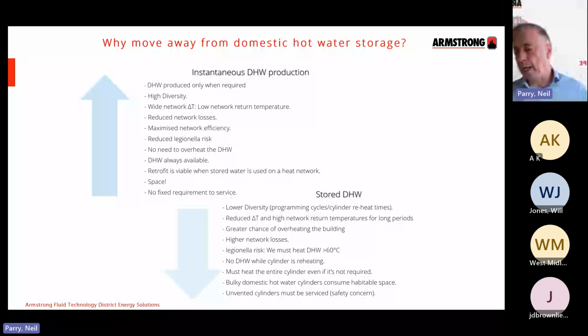With a stored system, you empty that cylinder into the bath. Again, that may take 5 minutes, but then you have to reheat that cylinder, and that takes a significant period of time. And all that basically means is you need to use a smaller diversity factor when you store domestic hot water compared to if you use an instantaneous system. And when you do the calculations, you find that the energy centre and the pipework are actually very similar, whether you go with one or the other. But of course, as I mentioned, you have to add that additional energy in if you're storing, and you lose your delta T. So it's got quite a few negatives associated with that.